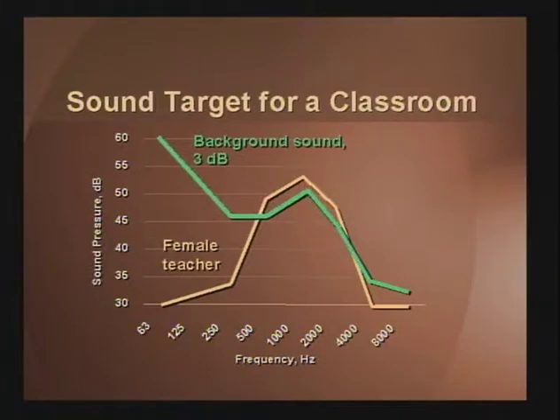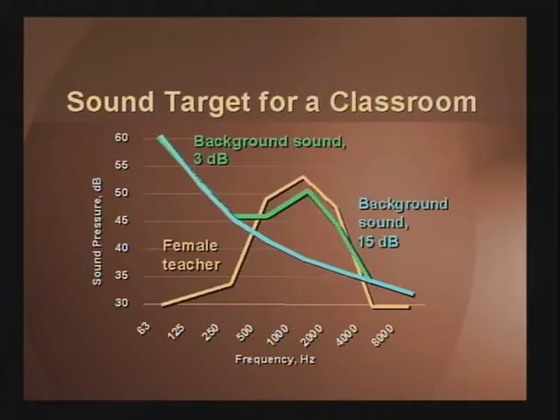Basically, the diffusers were inappropriately selected for this application. If we were to go back and reselect the diffusers, redesign the air handling system to get the noise in that frequency down, you would see a curve that looks something like this. That is a 15 dB spread between the teacher's voice and the background sound levels. And that, frankly, is what's being recommended for primary classes in the 1 to 3rd grade.